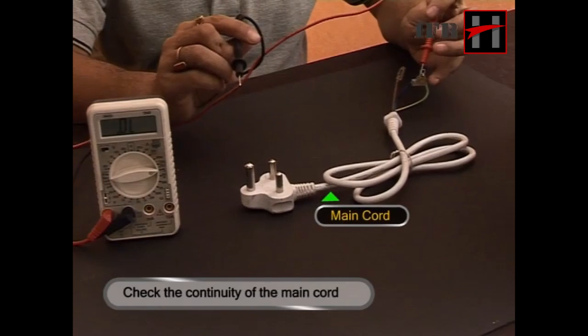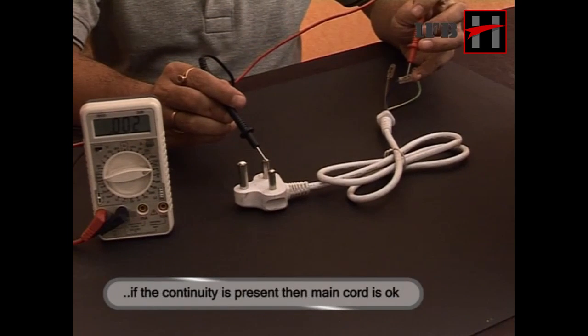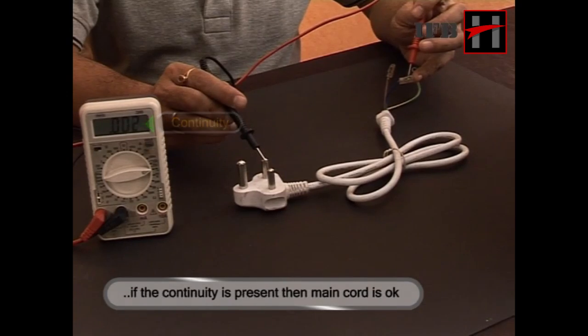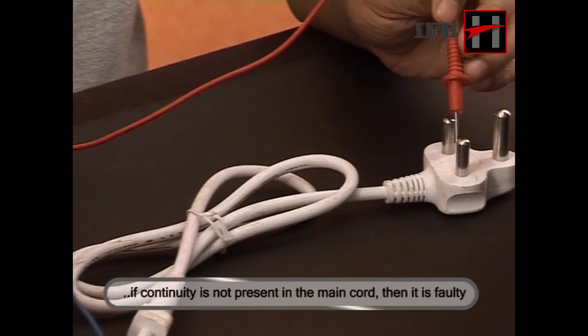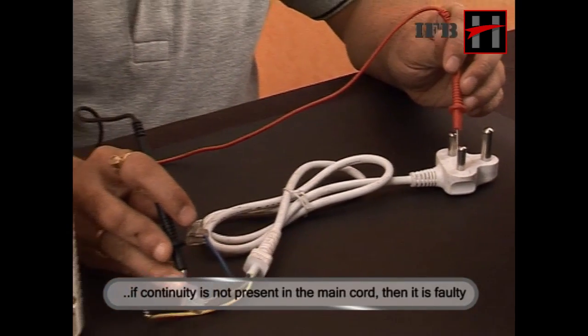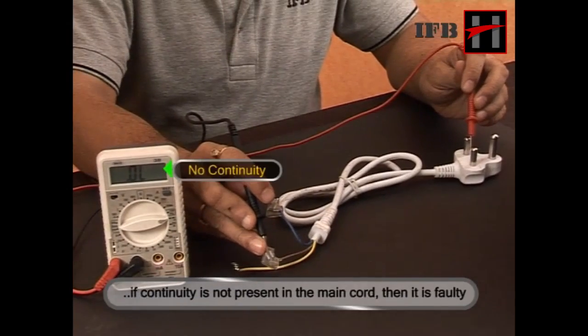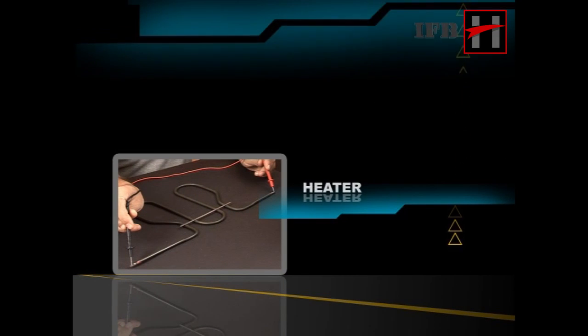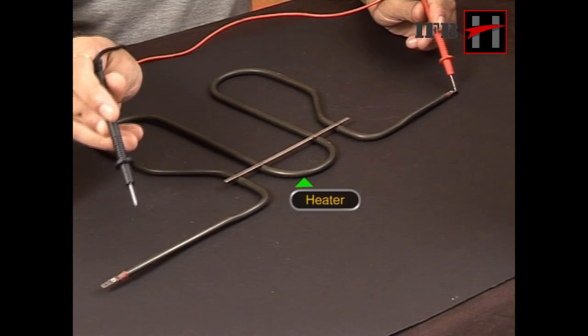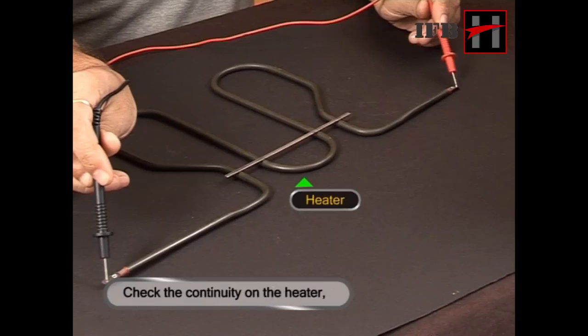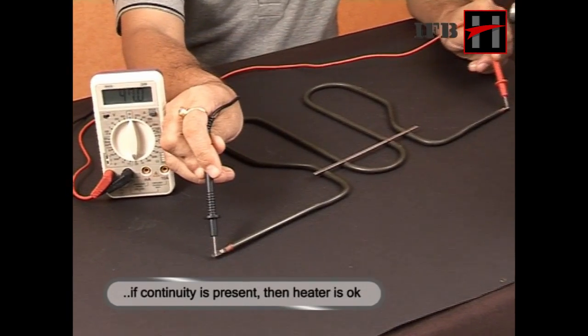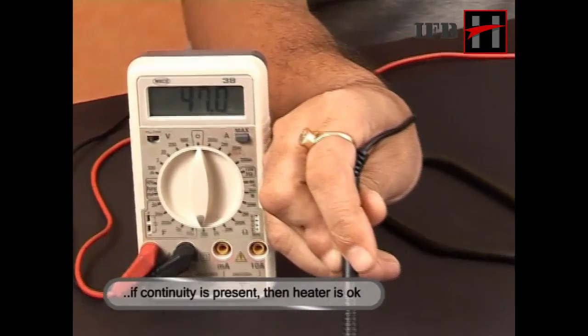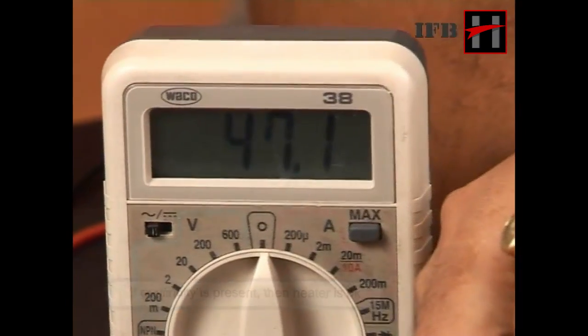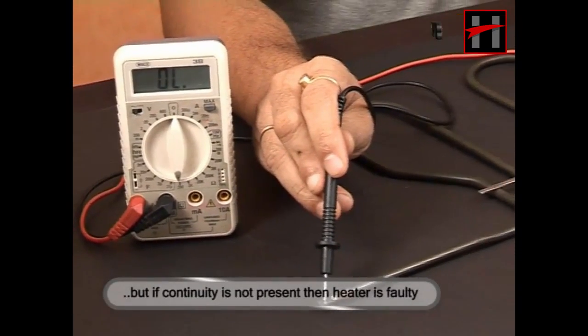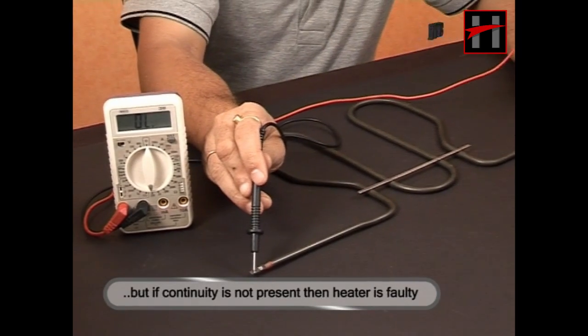Check the continuity of main cord. If continuity is present, then the main cord is OK. If continuity is not present, then there is some fault with the main cord. Check the continuity on heater. If continuity is present, then the heater is in normal working condition. But if continuity is not present, then there's some defect in the heater.